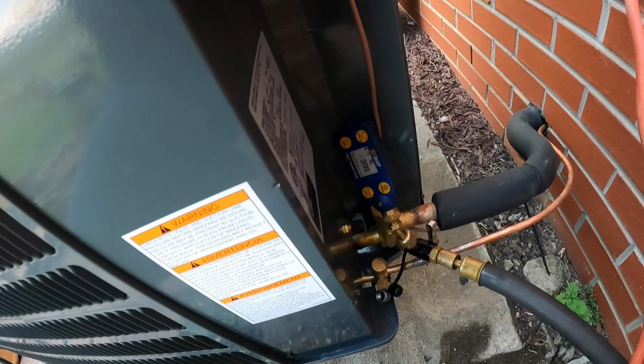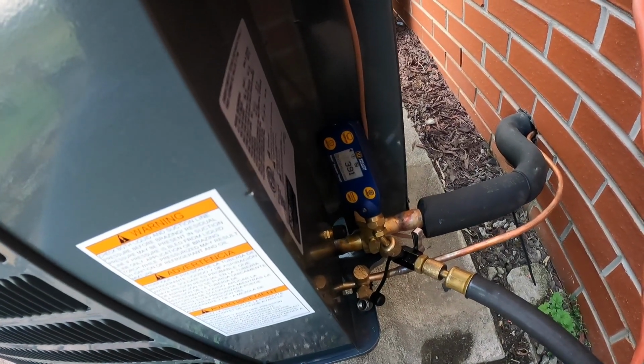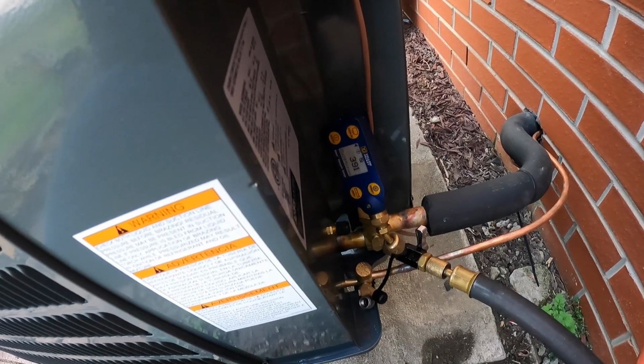And while we were in there looking at the zone sensor, the contactor pulled in, so it's calling for cool right now. So I'm going to let this thing sit here a few more minutes, and then I'm going to turn the charge loose.